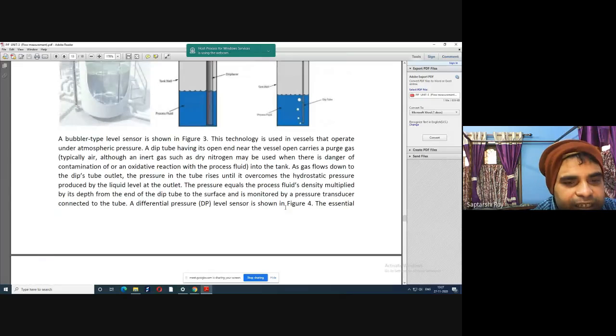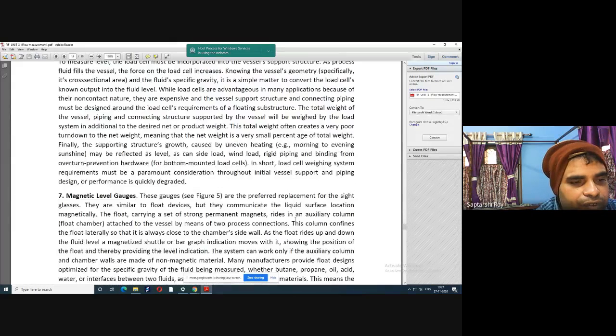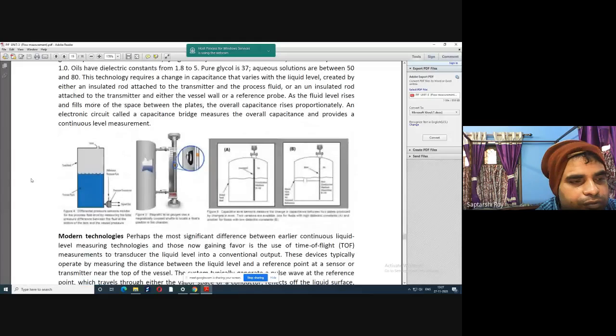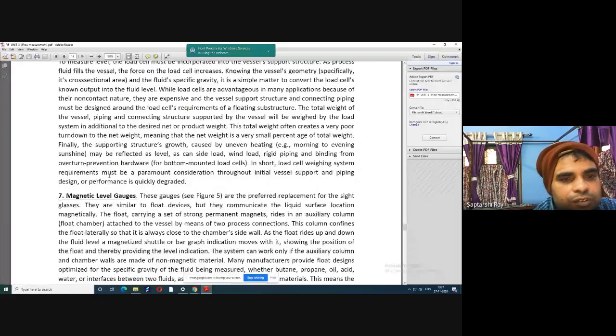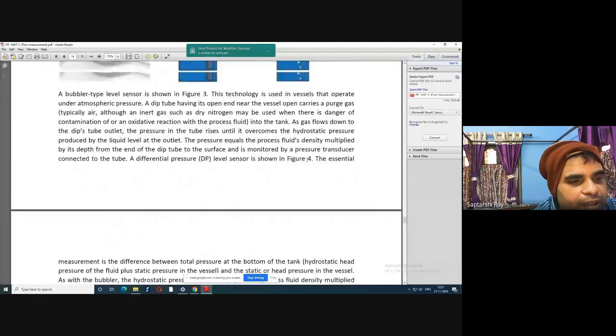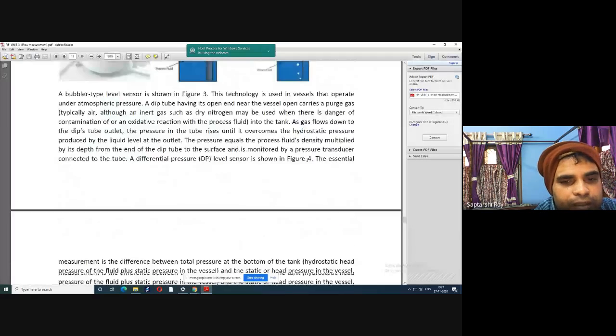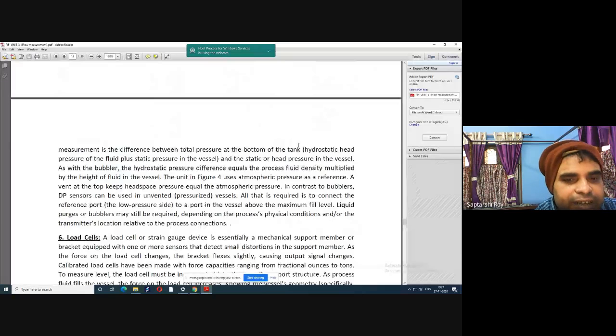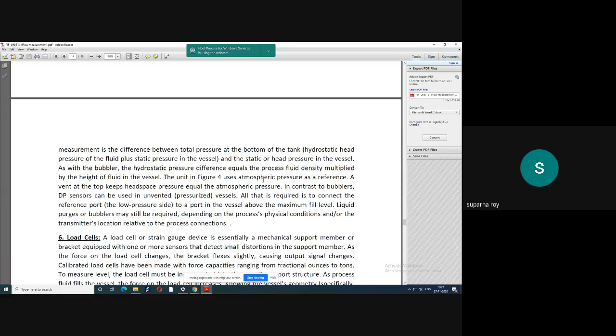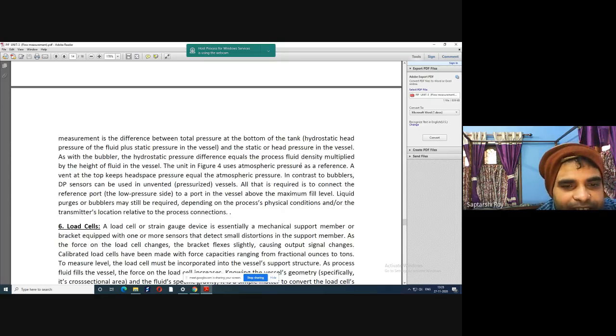A differential pressure level is shown in figure 4. The essential measurement is the difference between total pressure at the tank, or hydrostatic head pressure of the fluid plus static pressure in the vessel, and the static or head pressure in the vessel. As with the bubbler, the hydrostatic pressure difference equals the process fluid density multiplied by the height of fluid in the vessel. Uses atmospheric pressure as reference.